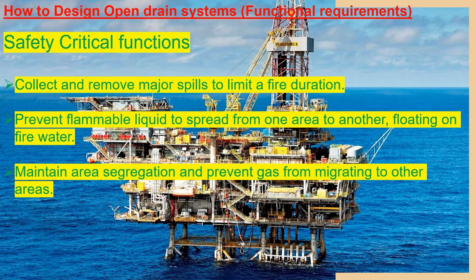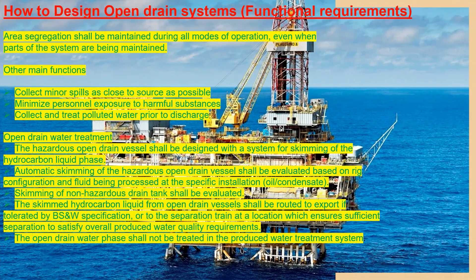Safety critical functions: collect and remove major spills to limit fire duration, prevent flammable liquid from spreading from one area to another floating on firewater, maintain area segregation, and prevent gas from migrating to other areas. Area segregation shall be maintained during all modes of operation, even when part of the system is being maintained.